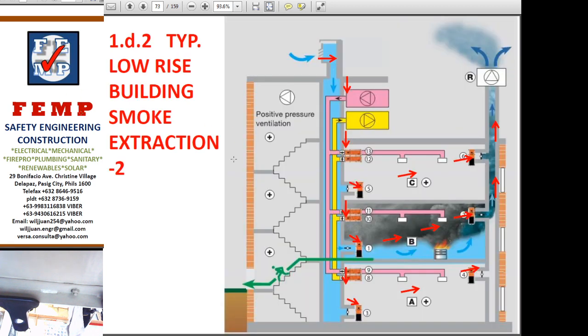Okay. Here is another example where the fresh air would come from the top of the building and would enter the building here and would get inside. Now you would notice here there are some control louvers.